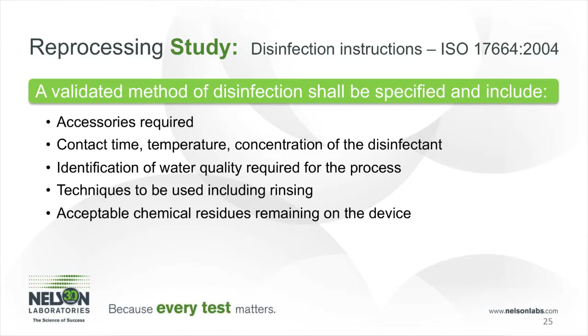ISO 17664 also specifies for disinfection that a validated method of disinfection shall be specified, and includes mainly a lot of the same items that are necessary for the cleaning validation. And that includes all accessories required for the disinfection process of the reprocessing. Also, the specific contact time, temperature, and concentration of the disinfectant.